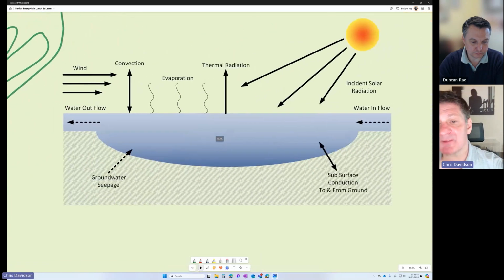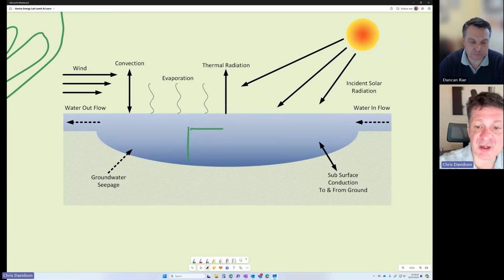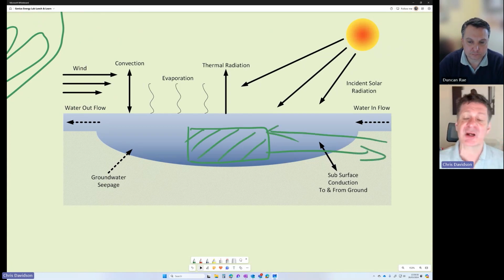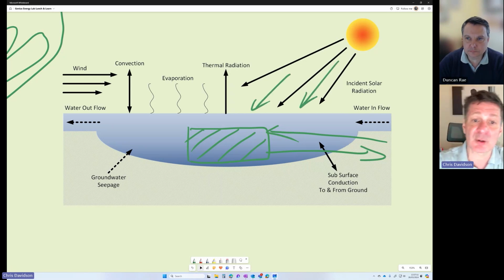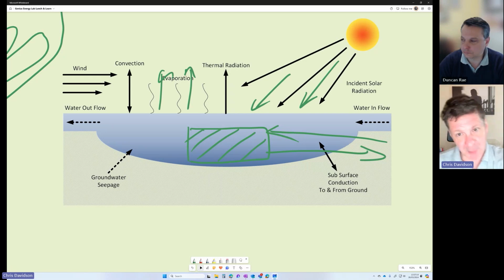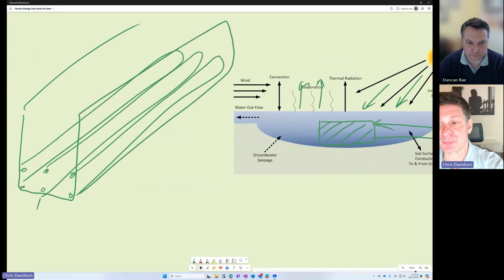There are other types of closed loop available to us. If we've got surface water like this, we can put heat exchangers in the bottom of that body of water, and we can take heat out of that heat exchanger or put heat back into that heat exchanger. Provided we exchange a similar or lower amount of heat with that water as the natural heat gains and the natural heat losses from it, then we've got, again, that sustainable system. The main heat gains are solar gains, and the main heat losses are actually via evaporation. Now, these can be very, very powerful systems, and at scale can be powerful enough to the point of economics, where it's worthwhile including some lakes or ponds and so on in the landscaping for a big house or even a multi-residential system. It can be combined with sustainable drainage, for example. So they can be a really powerful way of accessing closed loop systems.